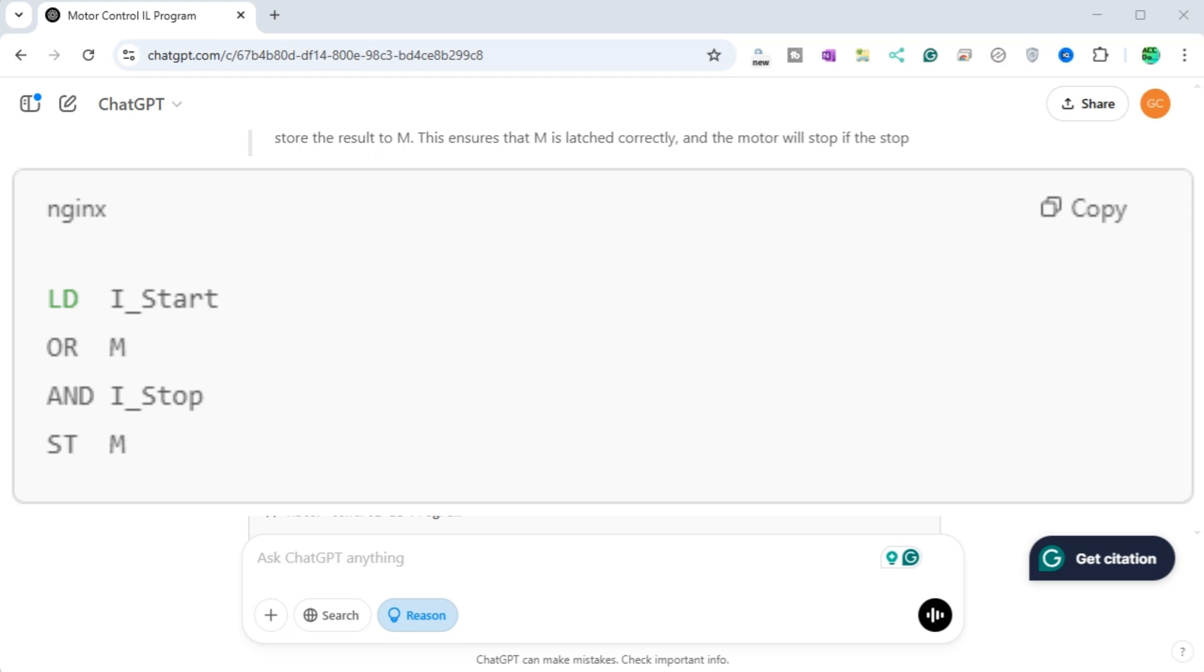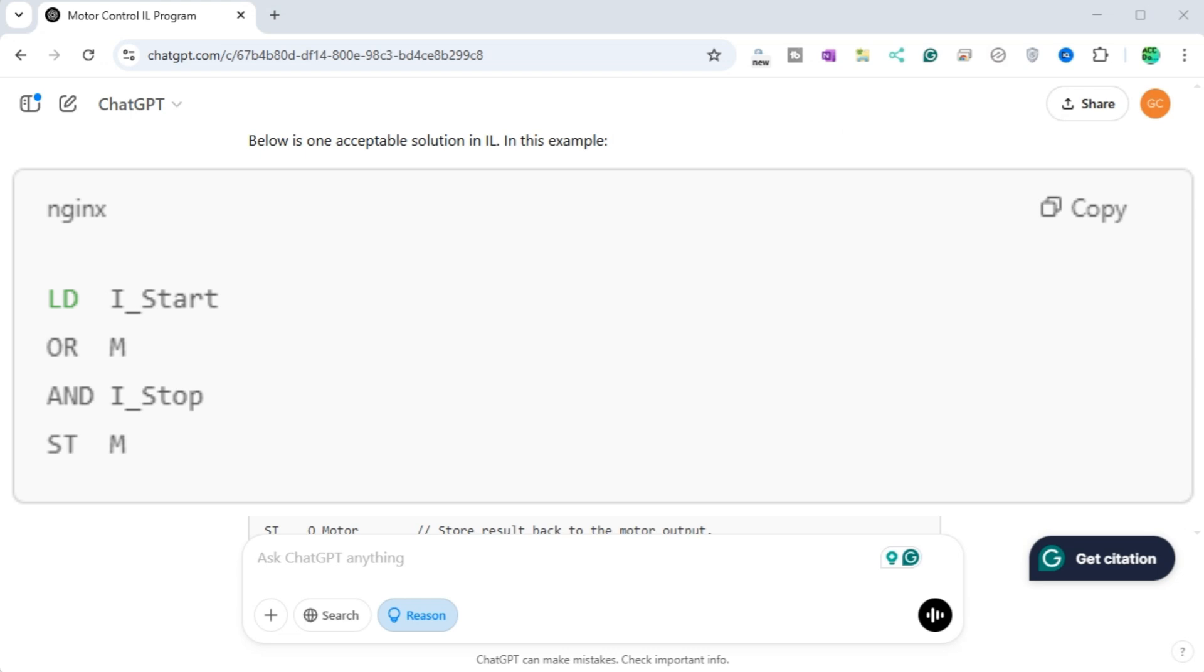First, evaluate I_start or M, then AND it with I_stop, and finally store the result to M. This ensures that M is latched correctly, and the motor will stop if the stop button is pressed, regardless of any prior state. After my tests, this approach avoids the unwanted behavior of leaving the motor running.